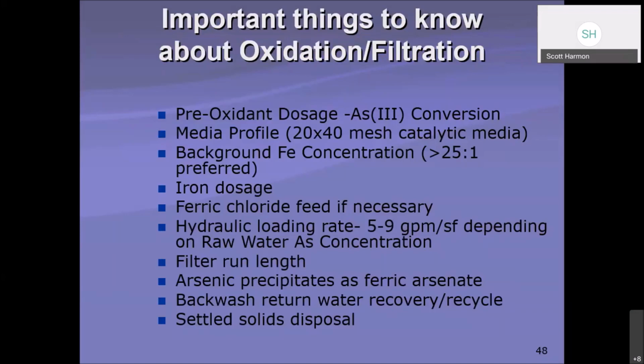Backwash, return, and recover, and recycle. Again, when we talk about the backwash, return, and things like that, we have to understand that we are concentrating arsenic. So the return and recovery water sometimes can be an issue, which we'll talk about later. And for sure, settled solids disposal will be an issue because those settled solids will have a concentration of arsenic that could be dangerous.